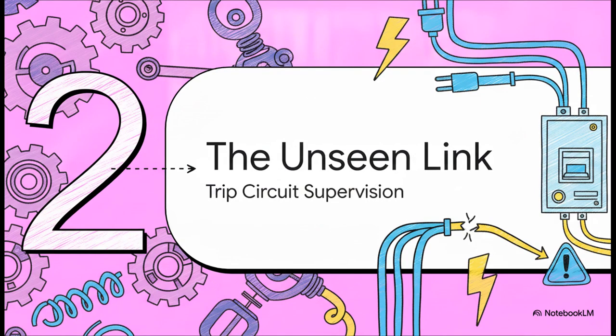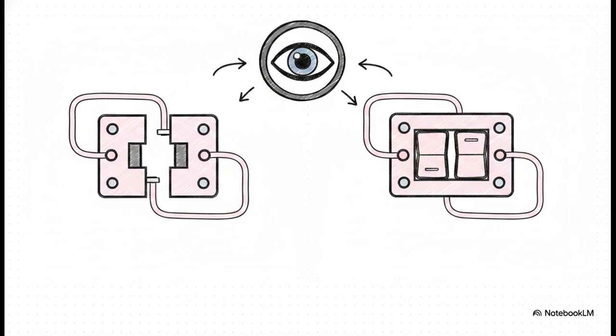Section 2. The unseen link. Trip circuit continuous supervision. Because mechanical health is really just one layer of this assurance. A mechanically perfect breaker is functionally useless if the control wire telling it to trip is broken. This brilliantly illustrates why the trip circuit supervision function, or TCSSCBR, is so vital. Think about it. A protection relay that is perfectly healthy is absolutely useless if the copper wire connecting it to the breaker's trip coil is compromised.